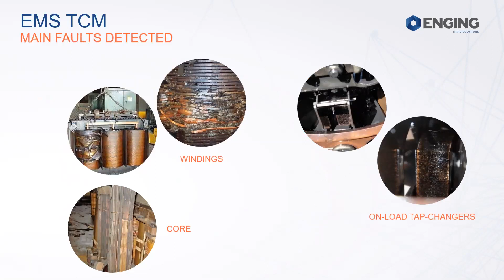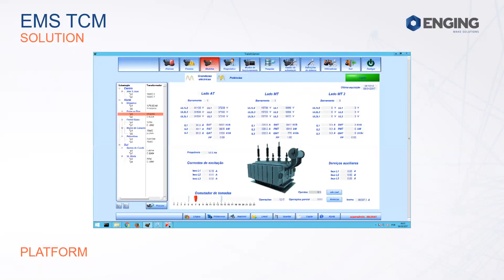Going on, this is the EMS TCM platform. And here you have a small example of what you can see in the software. So you have all the information concerning the transformer, okay? We have the excitation currents, we have the on-load tap changer, and basically we want to reach this layout. Basically, you have this information about the windings, about the core, and about the on-load tap changer. The 3 semaphore lights you have are at the top of the screen. In this case, this is a problem in the windings in the first phase.